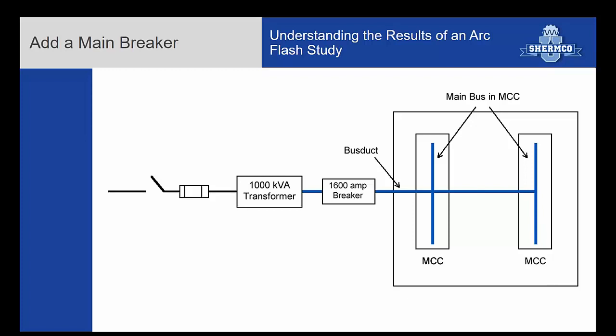Okay, so back to the MCC, what could we do? Well, one thing we could do, if we had this scenario where the MCC had high incident energy and we do need to rack on and off MCC buckets while it's energized, we could add a main breaker between the transformer and the MCCs. In that case, this little piece of bus here would still be dangerous, but we can develop settings to make everything downstream much lower. However, that's not always practical. Finding the space to put that breaker can be difficult when they built it to take as little space as possible. So if we want to add a breaker, we may not be able to on the secondary.